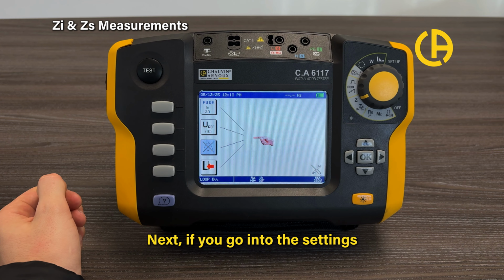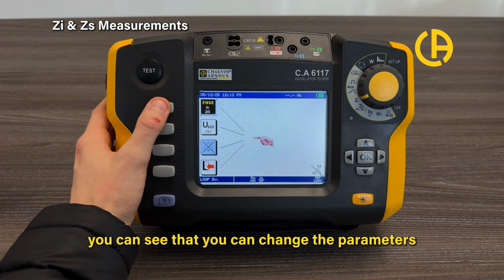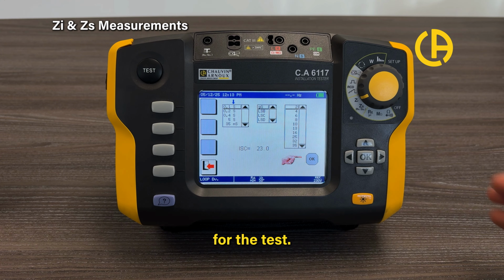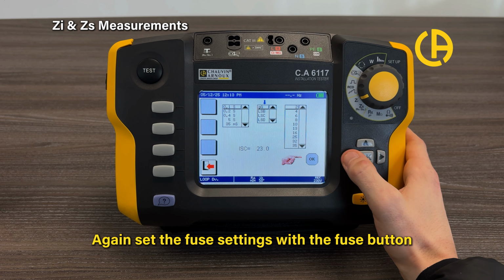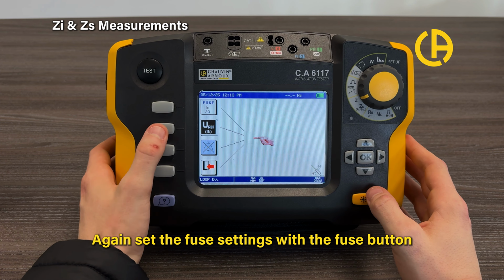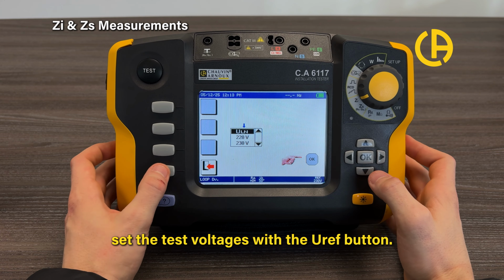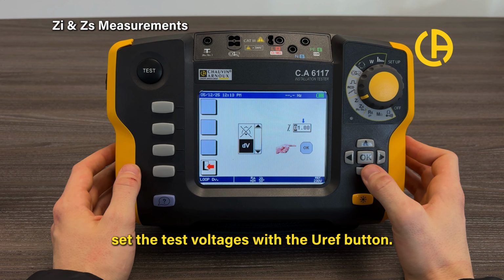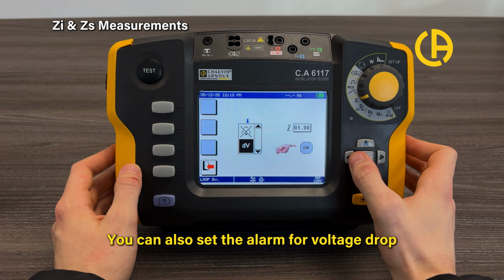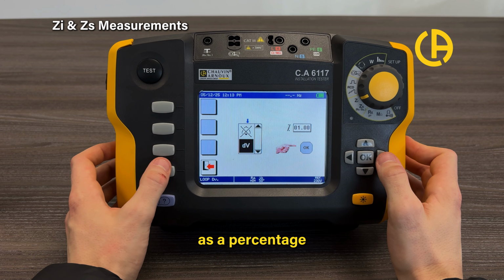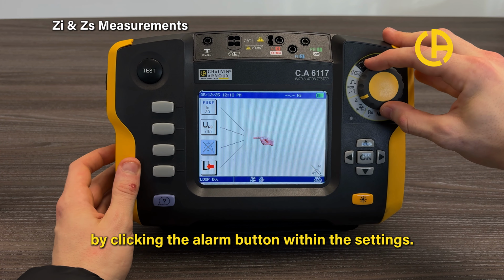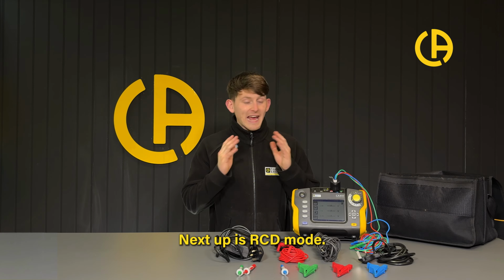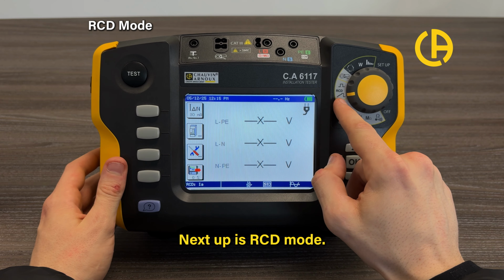Next, if you go into the settings, you can see that you can change the parameters for the test. Again, set the fuse settings with the fuse button, and also set the test voltages with the U reference button. You can also set the alarm for voltage drop as a percentage by clicking the alarm button within the settings. Next up is RCD mode.